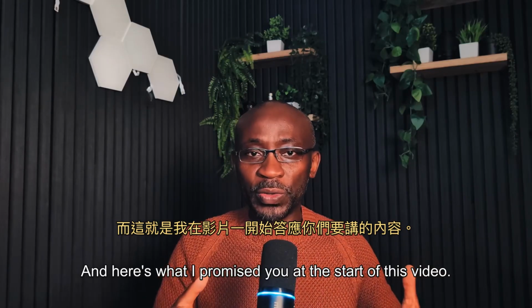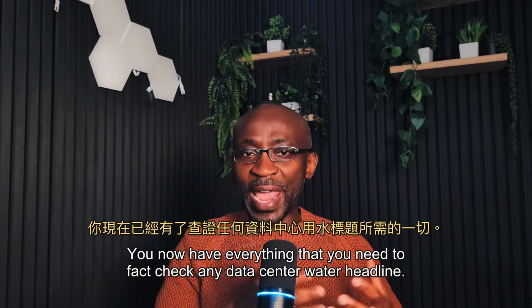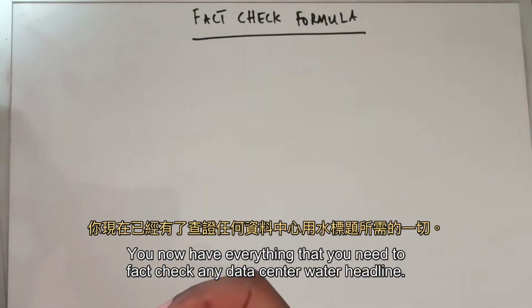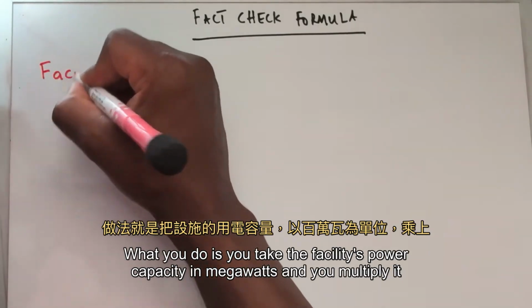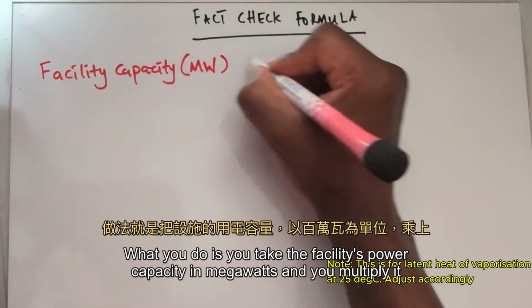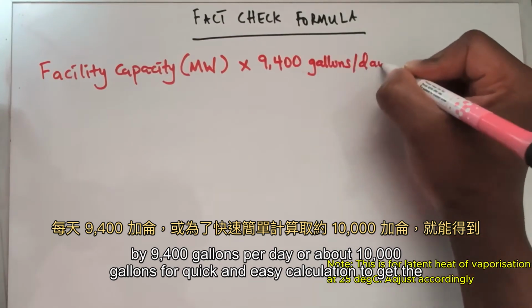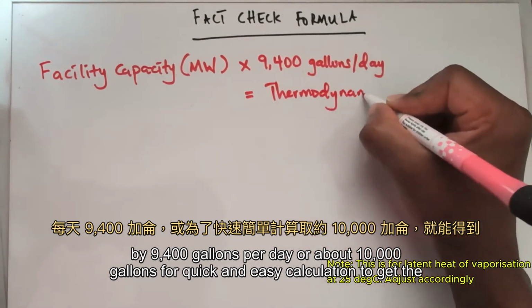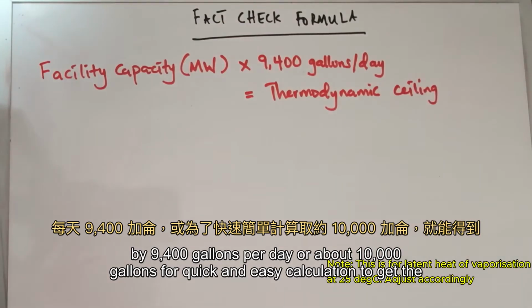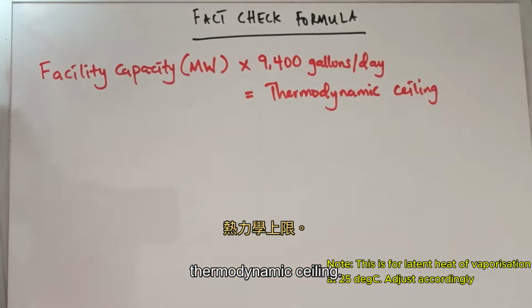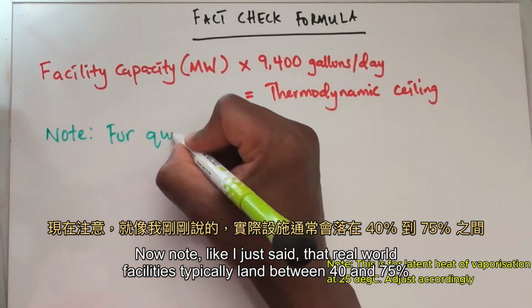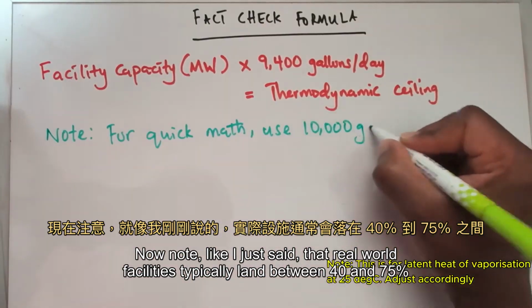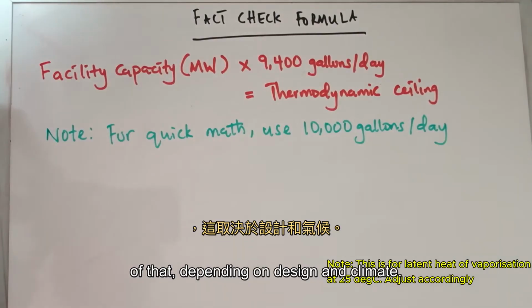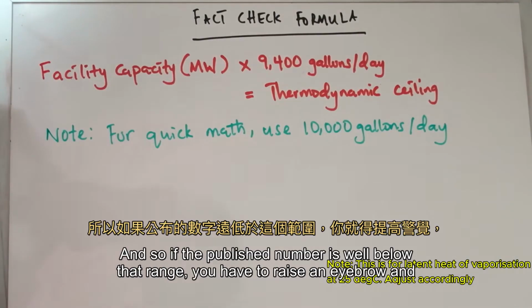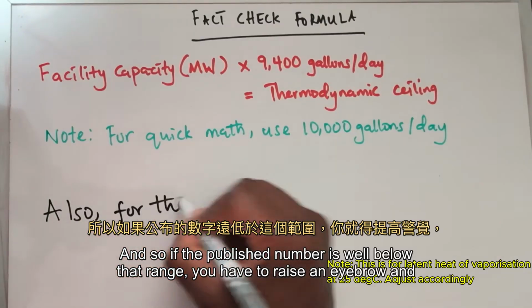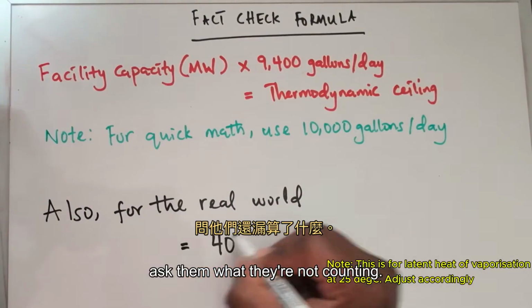And here's what I promised you at the start of this video. You now have everything that you need to fact check any data center water headline. What you do is you take the facility's power capacity in megawatts and you multiply it by 9,400 gallons per day, or about 10,000 gallons for a quick and easy calculation, to get the thermodynamic ceiling. Now, note, like I just said, that real-world facilities typically land between 40 and 75% of that, depending on design and climate. And so if the published number is well below that range, you have to raise an eyebrow and ask them what they're not counting.